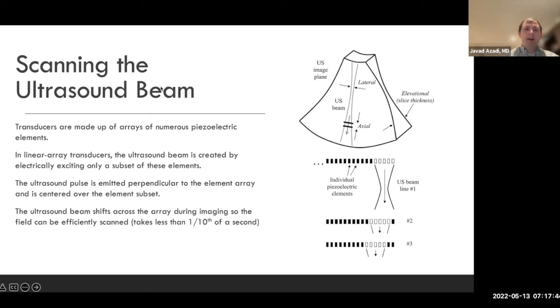And so how do we scan the ultrasound beam? Well, transducers are actually made up of numerous arrays of piezoelectric elements. It's not just one single piezoelectric element, as I alluded to earlier. So you can individually trigger or individually listen. You can shape the beam. Again, this is more engineering than it is radiology, but in a linear array transducer, the ultrasound beam is created by electrically exciting only a subset of these elements. The ultrasound pulse is emitted perpendicular to the array and is centered over the element subset. And then the ultrasound beam shifts across the array during imaging so that the field can be efficiently scanned.